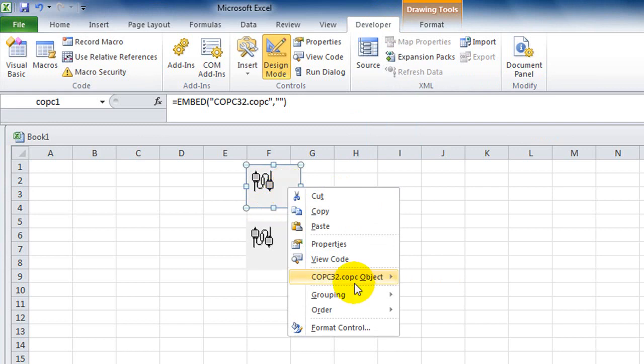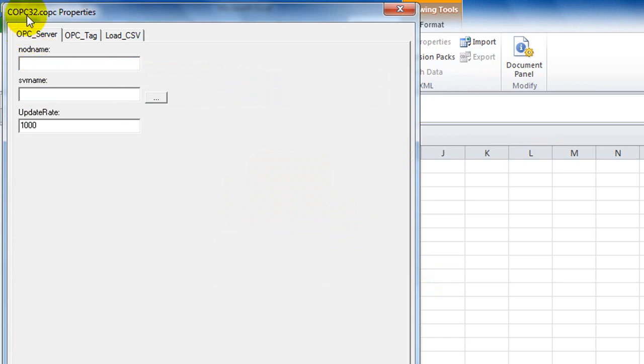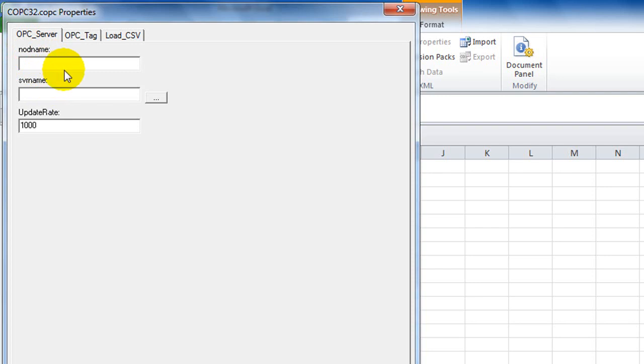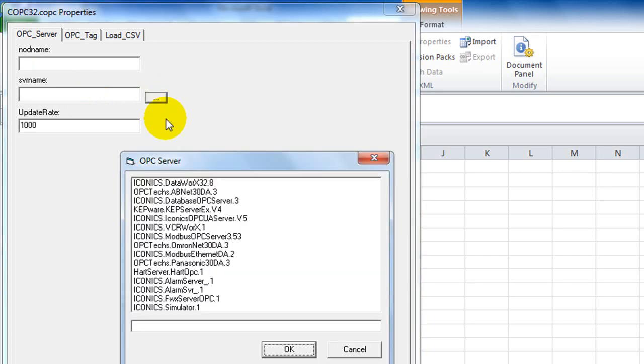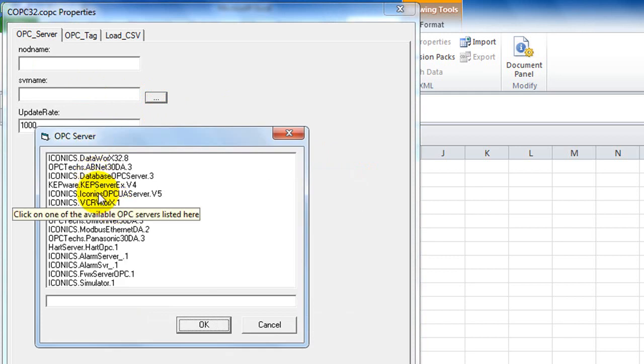Right-click on COPC1, choose COPC32 Object, then select Properties. This opens the COPC properties dialog where you can select the server name. If connecting to a local OPC server, you don't need to enter anything in the node name text box. But if you want to connect to a remote OPC server on another PC, you need to specify that PC's IP address. I'll be connecting to the local OPC server, so I can click the button to choose the OPC server on this system.